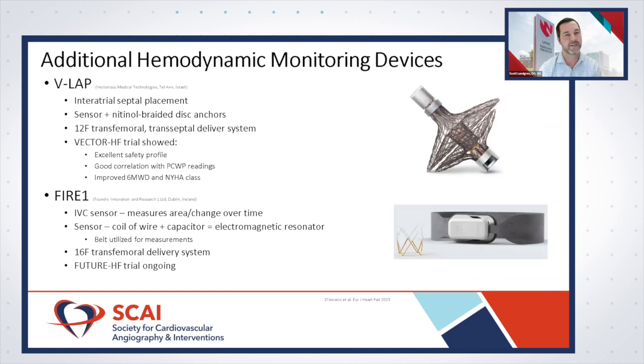Stepping out of the lungs, there are additional hemodynamic devices currently in clinical trials. The V-LAP device is an interatrial septal placement device. It has a sensor that enters the left atrium and directly measures pressures, with two nitinol-braided disc anchors to keep it in place. It uses a 12 French transfemoral sheath and a transseptal delivery system provided with the device.